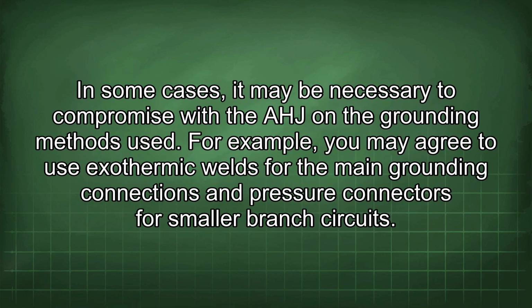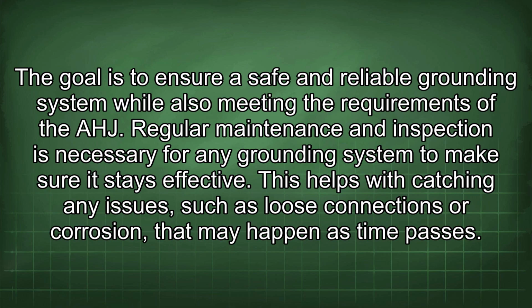In some cases, it may be necessary to compromise with the AHJ on the grounding methods used. For example, you may agree to use exothermic welds for the main grounding connections and pressure connectors for smaller branch circuits. The goal is to ensure a safe and reliable grounding system while also meeting the requirements of the AHJ.